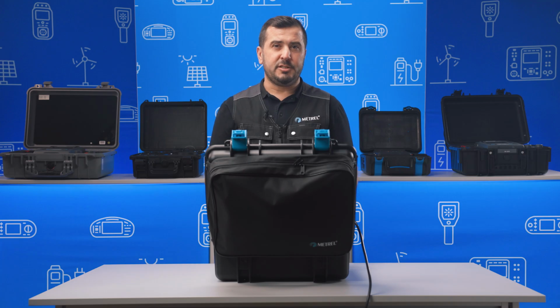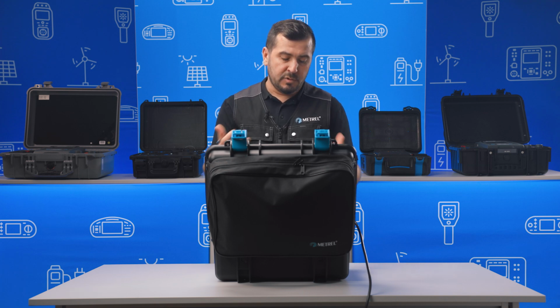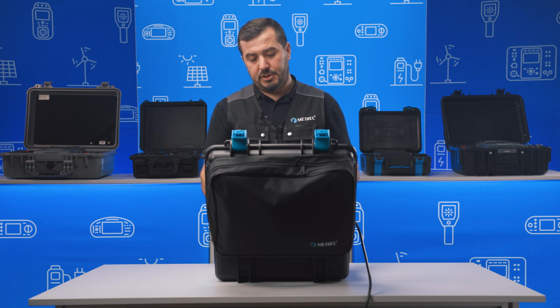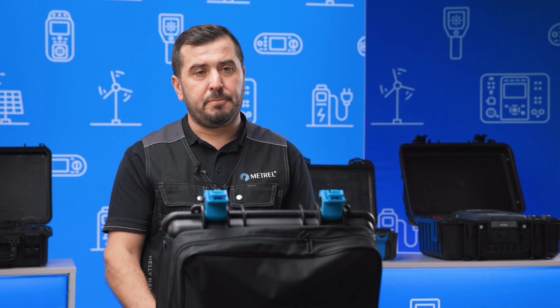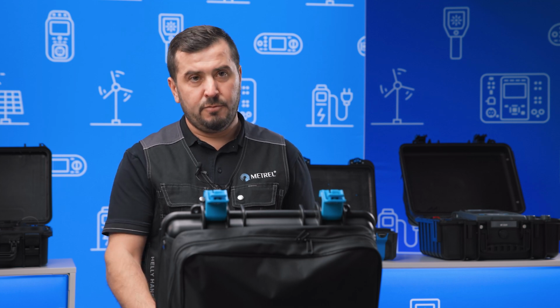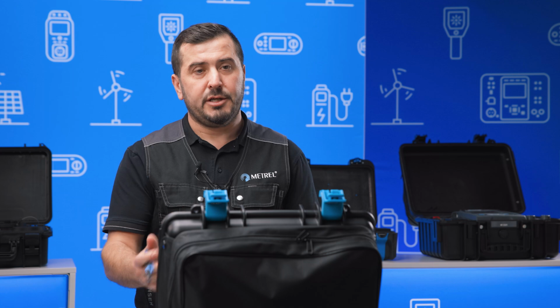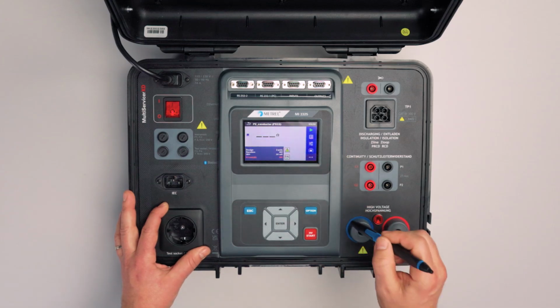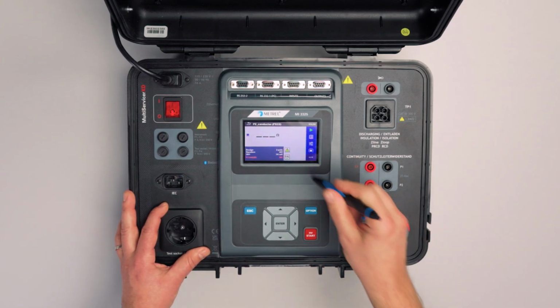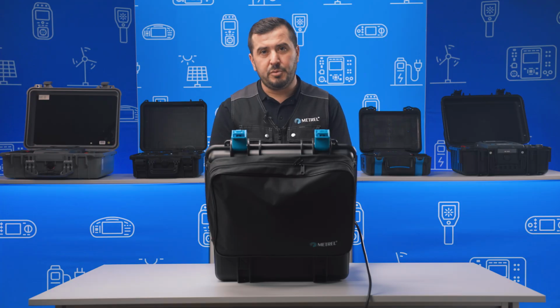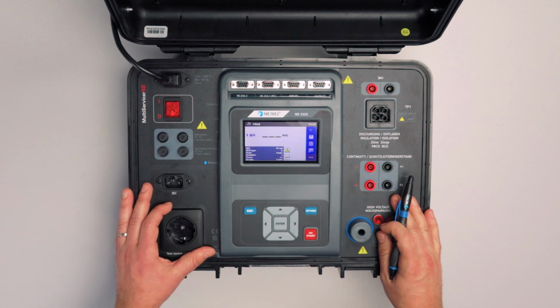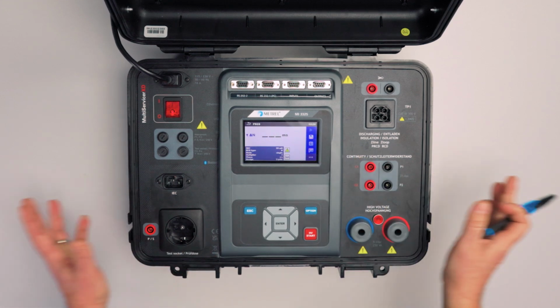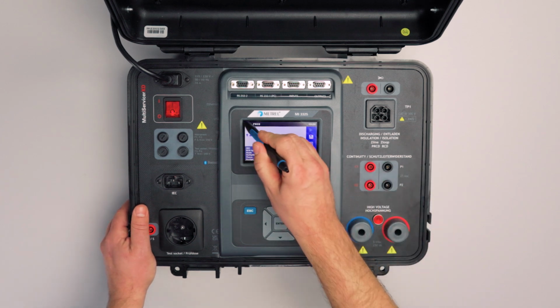Then, when testing special types of RCDs, there are also two additional functions. When we are testing RCDs that need to be supplied with voltage for triggering them, we also have to test the PE conductor resistance, and for this we have the active PE conductor test. And the last option is to test the portable RCDs built inside the extension leads.